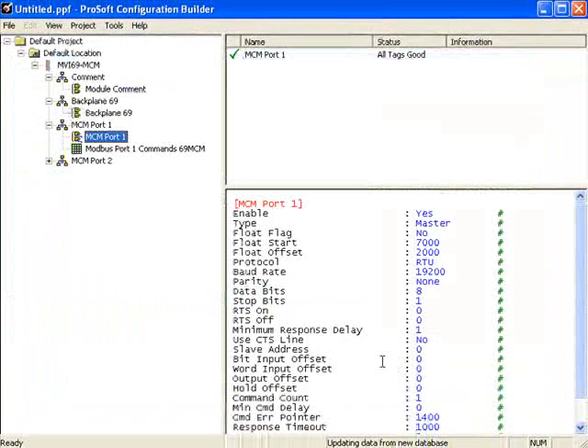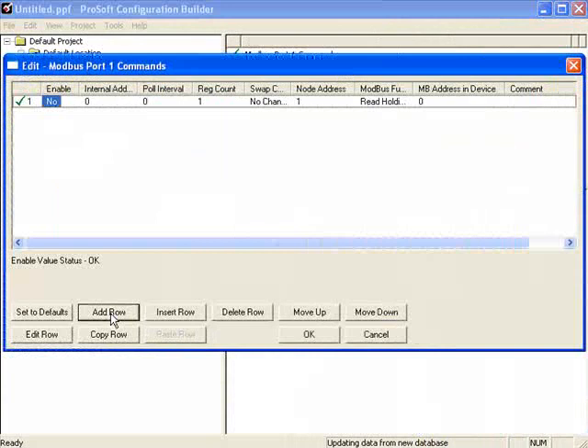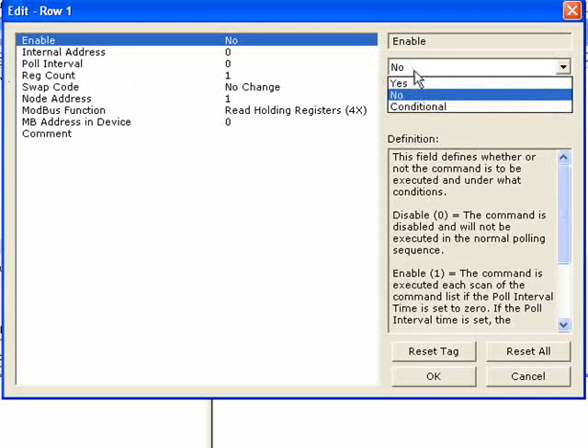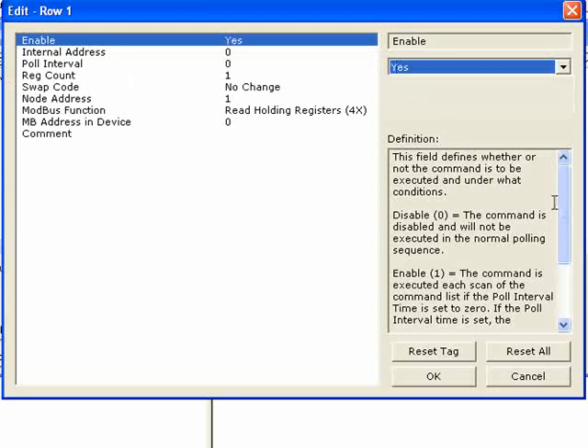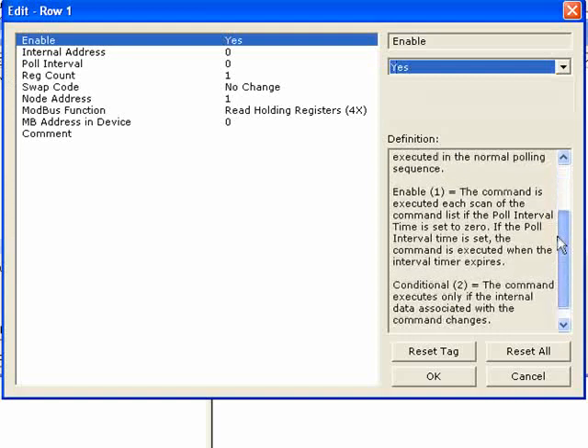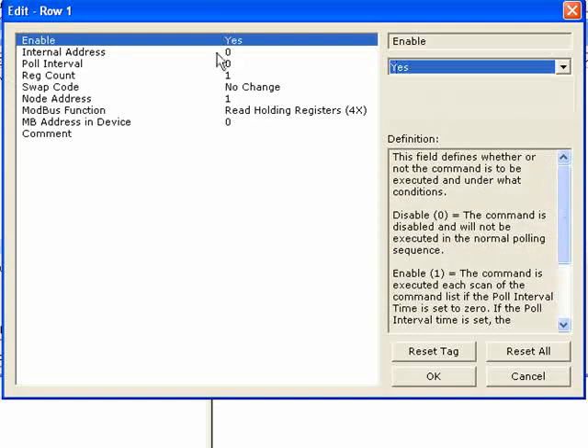Now let's go into the Modbus master commands. I'll click on Modbus port 1, then double-click on Modbus port 1 commands for the MVI69 MCM. We can click Add Row to add a Modbus command. Double-click on any portion of that row to see the command settings. The first setting is the Enable Column, which defines whether the command is enabled and how it gets executed. An Enable code of Yes is a continuous command — the command always executes. A 0 or No means the command is not enabled.